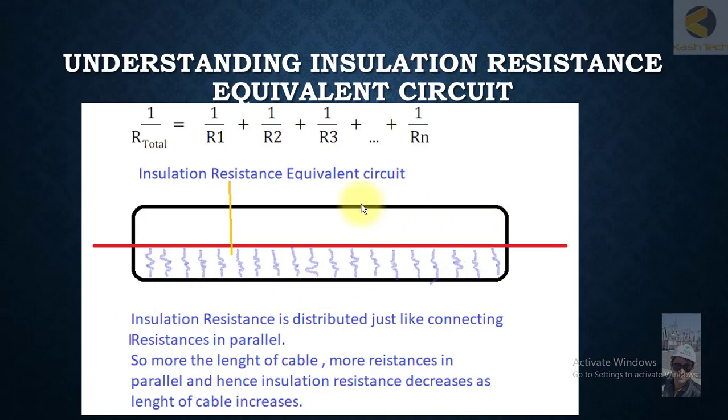So insulation resistance is distributed just like connecting resistances in parallel. So more the length of cable, more resistances in parallel, hence insulation resistance decreases as length of cable increases. Now you can imagine the insulation resistance of any electrical equipment or cable and you can analyze yourself.